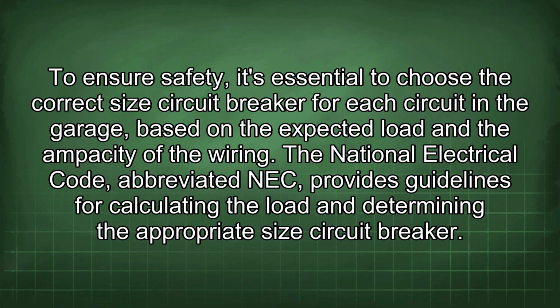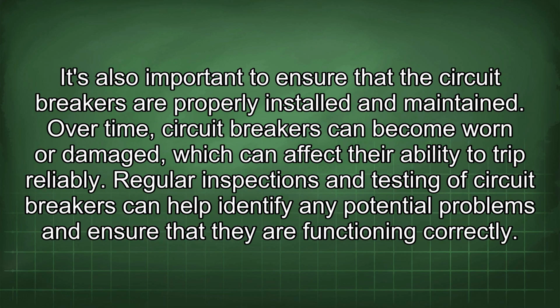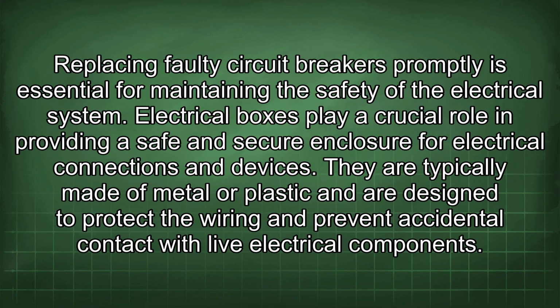The National Electrical Code, abbreviated NEC, provides guidelines for calculating the load and determining the appropriate size circuit breaker. It's also important to ensure that the circuit breakers are properly installed and maintained. Over time, circuit breakers can become worn or damaged, which can affect their ability to trip reliably. Regular inspections and testing of circuit breakers can help identify any potential problems and ensure that they are functioning correctly. Replacing faulty circuit breakers promptly is essential for maintaining the safety of the electrical system.